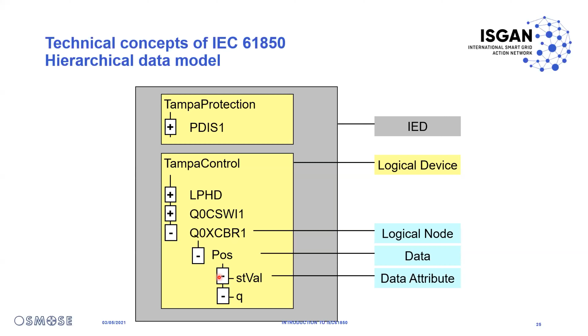That's one of the elements of the standardized data model, and it's further defined that such a logical node XCBR contains a data object called POS, and that's where we find the position of the breaker. In particular, we find the position at the data attribute stVal, or status value. So that's the concept of the data model in IEC 61850.